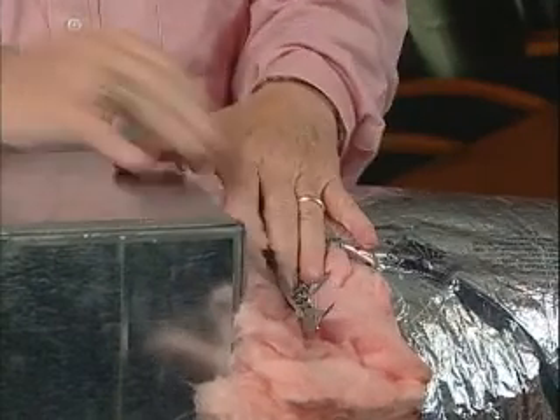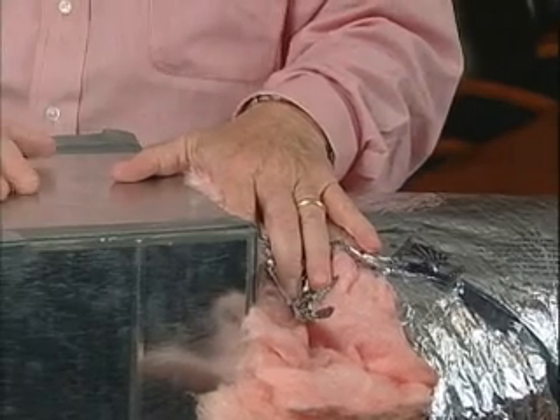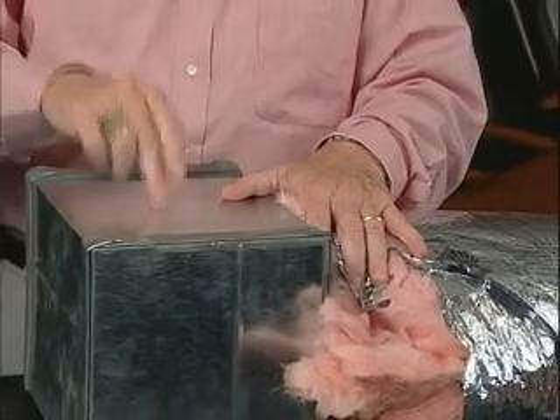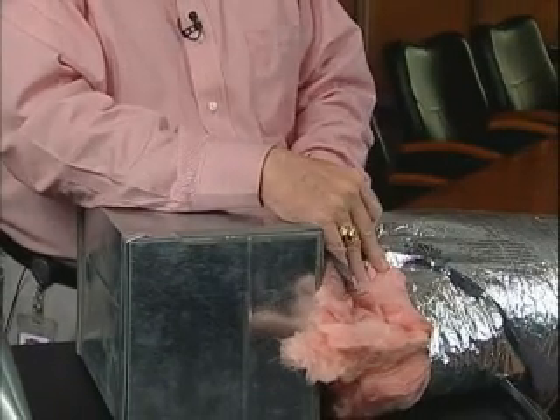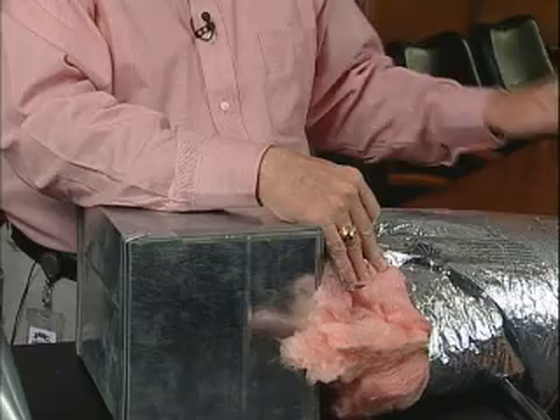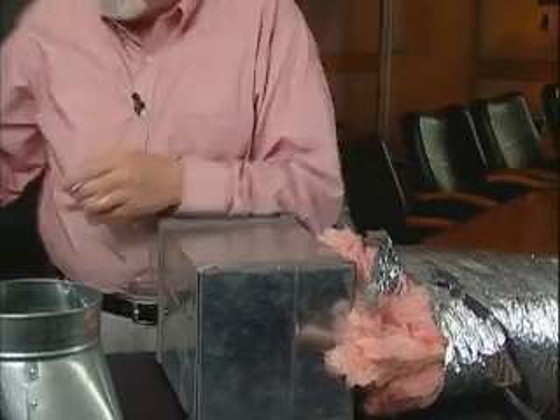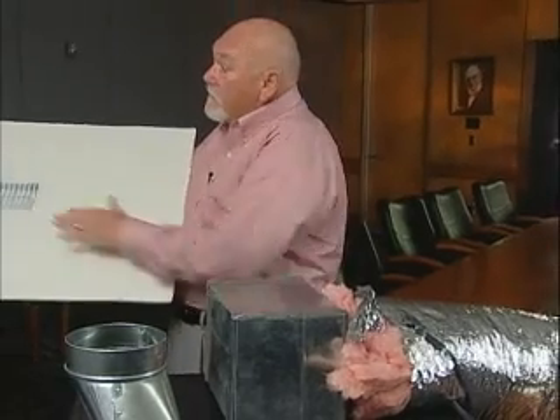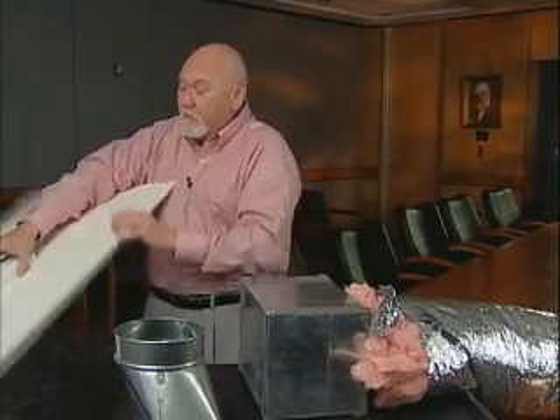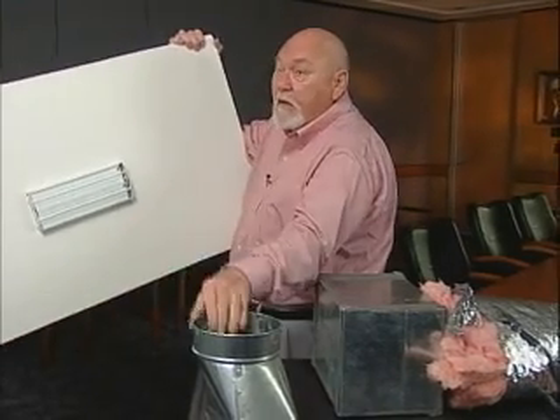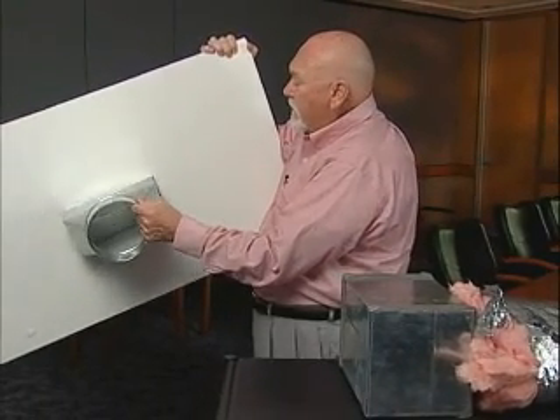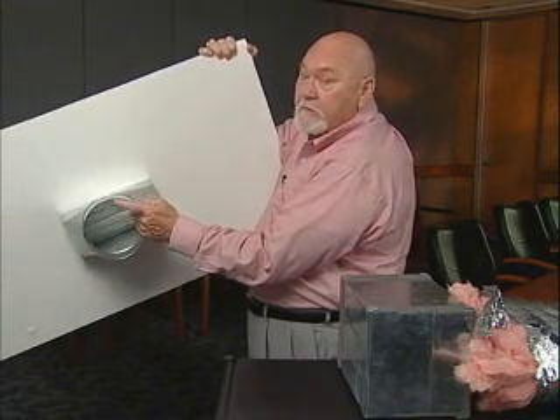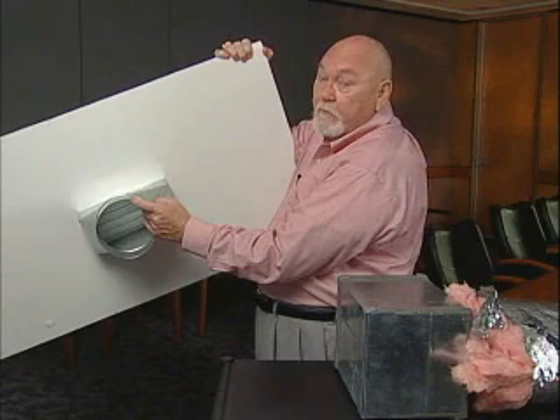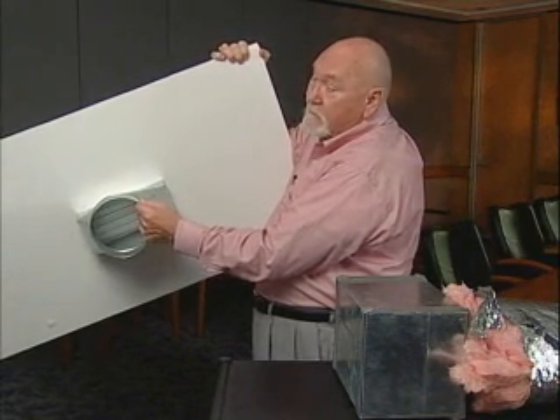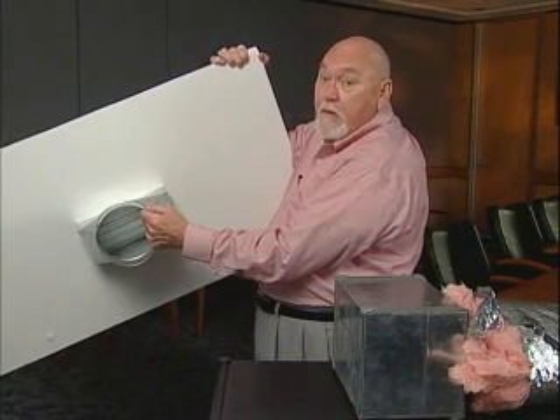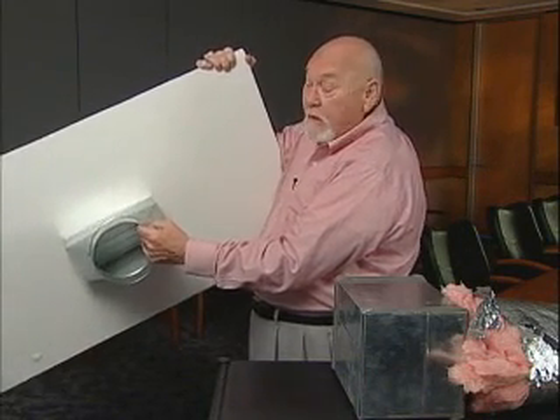So what we have, in essence, with a sealed system is air being driven by the fan into the main supply, into the secondary takeoff, the ductwork that's leading to the vent. And let's say that this is your floor. This is what you see in your home. This is under the house, and this boot fits over this vent. This is where the ductwork attaches right here. When you make this attachment, you want to make sure that attachment is done with mastic also to ensure that it doesn't suck air there.